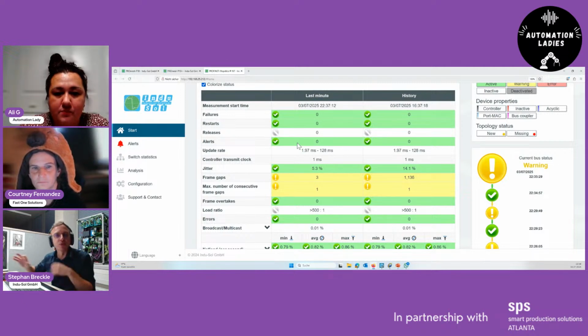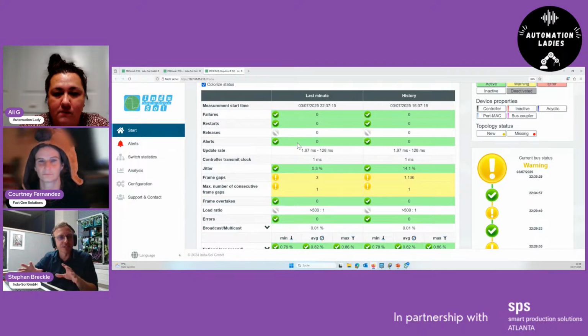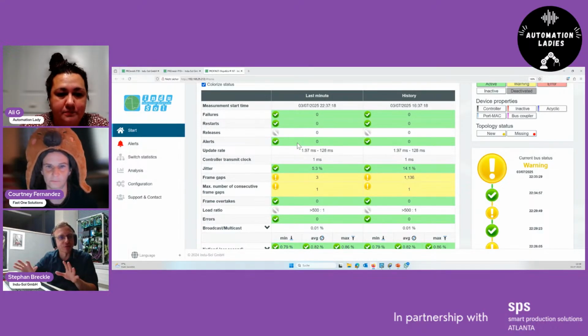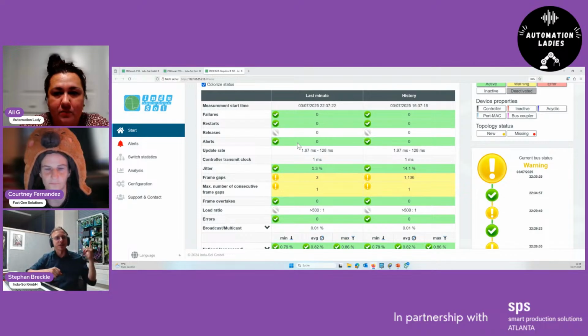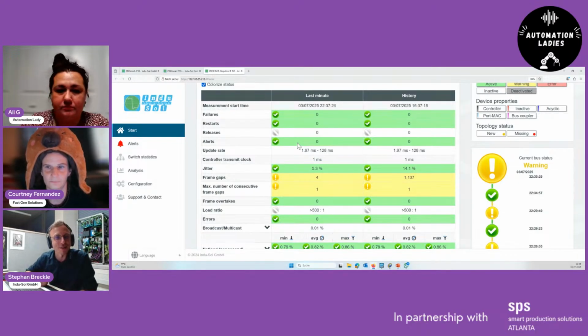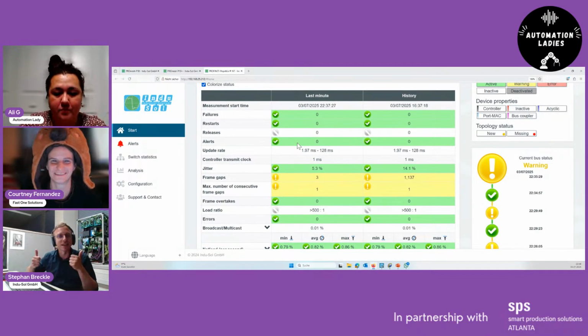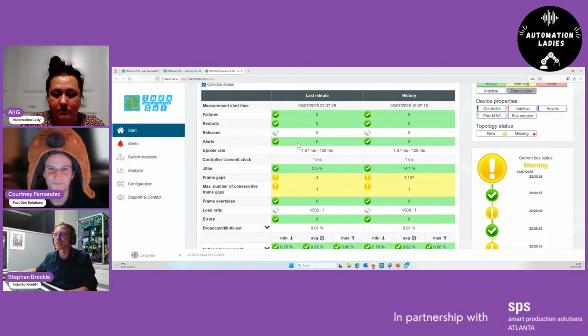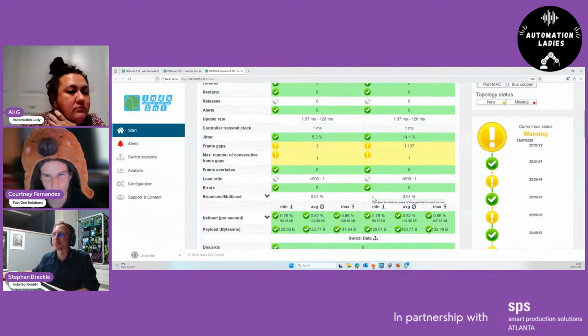This is because each PLC has an internal watchdog. If you don't hit the watchdog, everything keeps running, and for the operator everything looks nice. On my rack, everything shows green, so the PLC thinks everything works very well. You can run your system without thinking about maintenance, but internally we already have some issues.